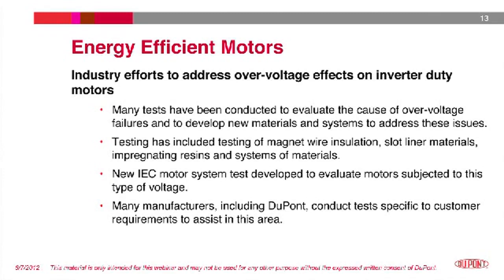The industry has recognized the need to provide new test methods for addressing these problems. Tests have been set up to evaluate insulation materials in systems, to evaluate the effect of increased voltage levels on slot liner materials, magnet wire insulation, and combinations or systems including impregnating resins. To address the higher failure rates in this type of equipment, the IEC recently added periodic testing of corona inception levels for motorette testing of insulation systems designed for severe applications such as seen with inverter duty motors. DuPont has conducted such testing as part of its work with customers in this area.